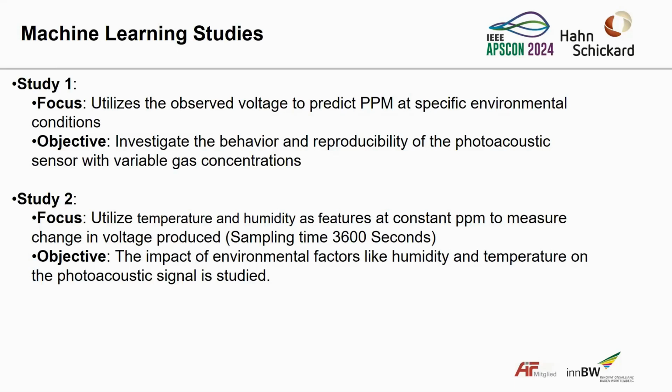In the second study we essentially do the same, but this time we use the same setup and vary the temperature and humidity response. We also do it at constant ppm, and we want to see whether the temperature and humidity influence is also repeatable for the sensor signal.